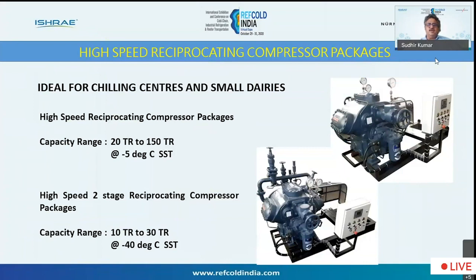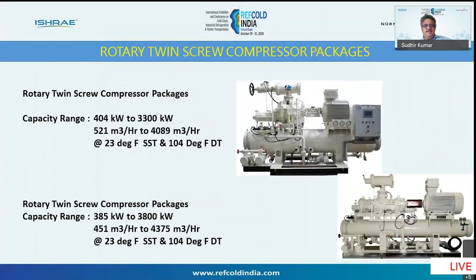And also you can have two-stage systems. If you are having a small butter deep freeze, then you can use a small reciprocating compressor. Then the latest trends are rotary screw compressors, twin screw compressors, which range from a capacity of say 100 TR to 1000 TR. We have nowadays dairy projects which are going up to 2000 TR in a single dairy project. So if you're going for a bigger project of 2000 TR, which is approximately 7000 kilowatt refrigeration, then it is not possible to go in with a reciprocating compressor package. It is better to go in for bigger compressors. So we start using screw compressors.